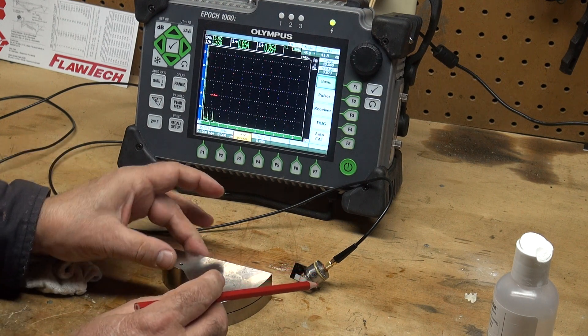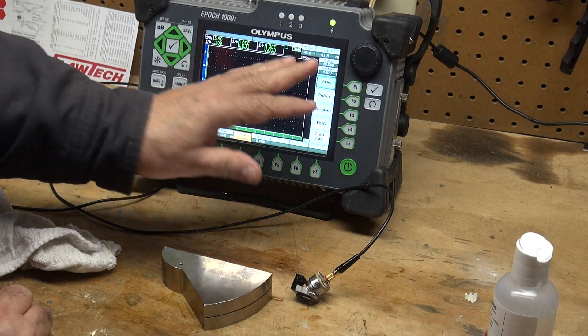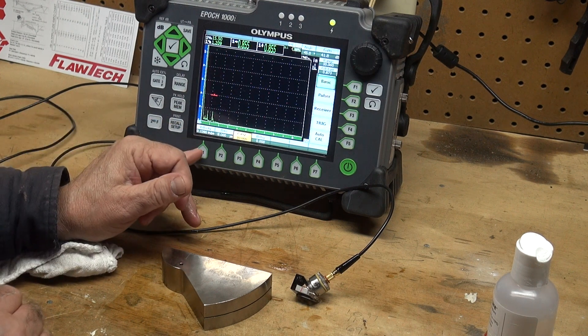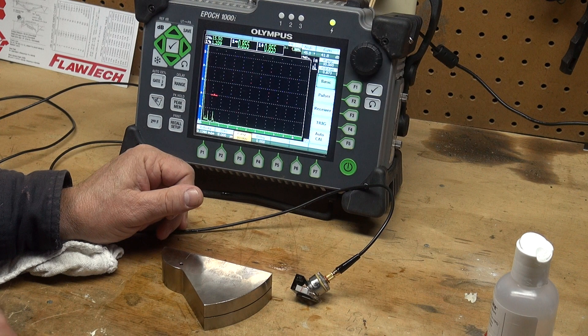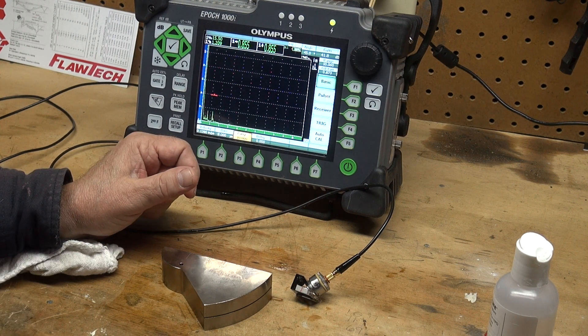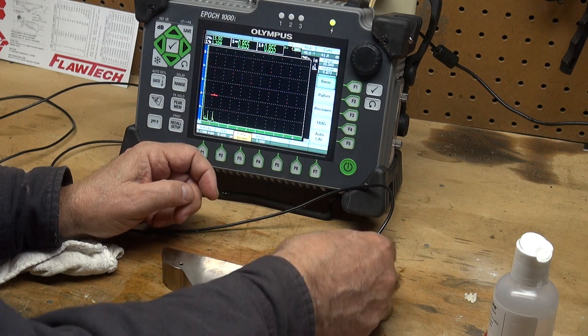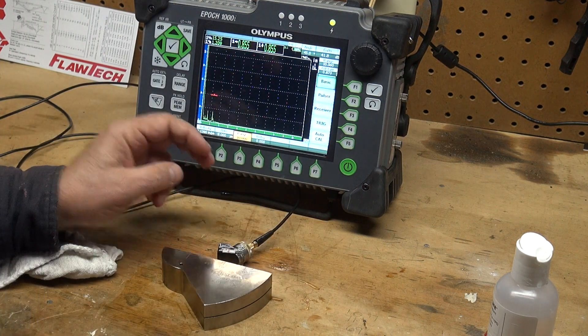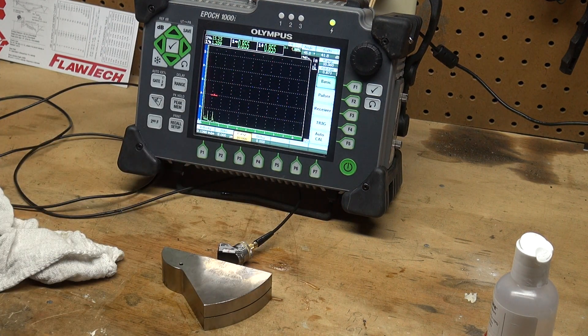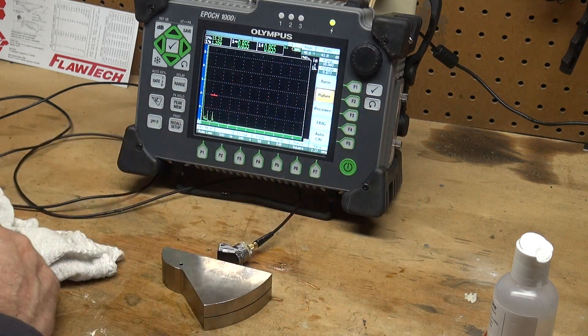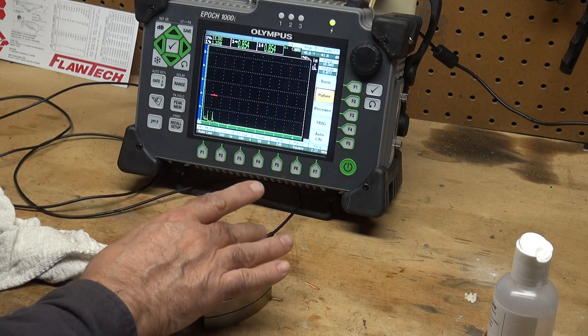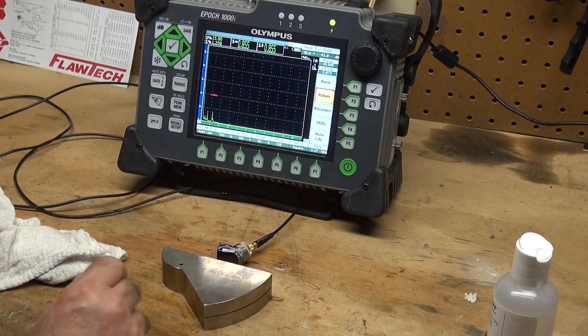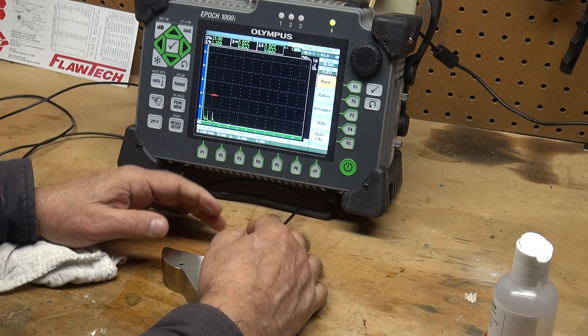So let's start by changing the range to 10 inches. Set my velocity at 0.128 inches per microsecond, your standard shear velocity in mild steel. Zero set to zero, my range is set to 10 inches. And of course in the trig I have 45 degree set for my angle, and in my pulser 2.27 megahertz. I want to make sure that your machine closely matches your transducer frequency.